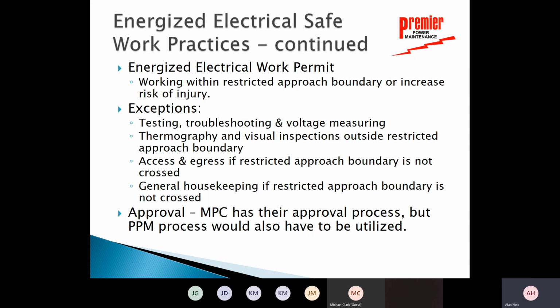We've got the restricted approach boundary, which is the limit for a qualified person. If you have a tool in your hand and you get inside that restricted approach boundary, that requires an energized work permit. Now, there are exceptions, and Marathon lays out the exceptions just exactly as NFPA 70E does. We'll go through those things. We can test, we can troubleshoot, and we can do voltage measuring inside that restricted approach boundary, and that does not require an energized work permit.